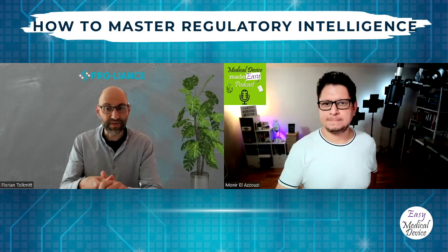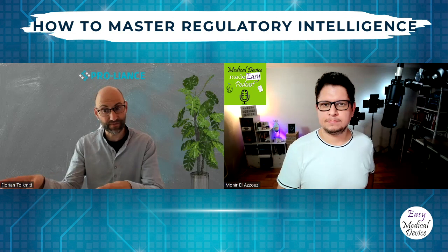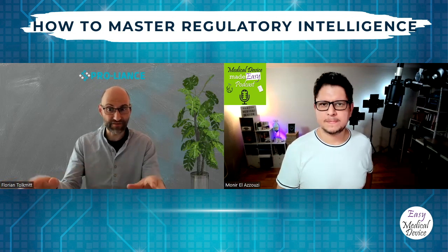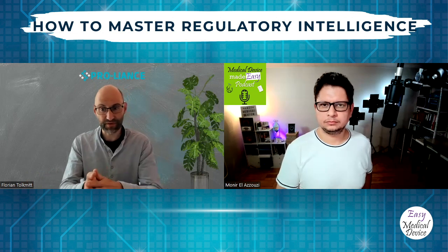Yeah, it's actually all those companies that have legacy devices that want to transfer to MDR. So this is the main general condition. Of course, there are more that we're going to talk about, but these companies also have to have had a valid MDD certificate in place, and I'm also including the AIMDD, of course. And that certificate had to be valid at the publication date of the MDR amendment, which was March 20th, 2023. Or if it was not valid anymore, then they needed, at that point in time, an agreement with a notified body already in place, saying, okay, we are going to transition with the timeline that we're going to talk about as well.